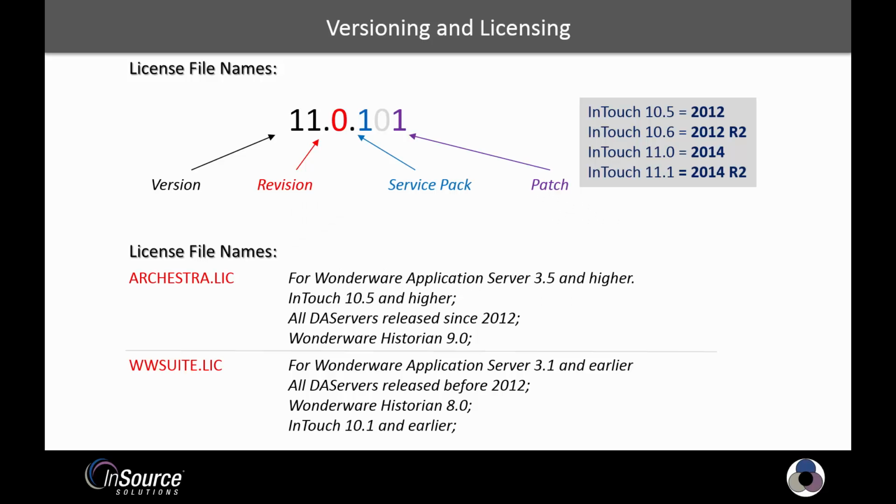Your InTouch application, in order for it to run, needs to be enabled. However, only a license can enable the InTouch application. First off, we have two types of files that when a customer purchases a license from us, they receive a pair of files. One is called the Archestra.lic and the other is called wwsuite.lic. The only difference has to do with the version of the software that you're running. For InTouch, anything older than version 10.5 will require the wwsuite.lic license. Anything newer will require the Archestra.lic license.